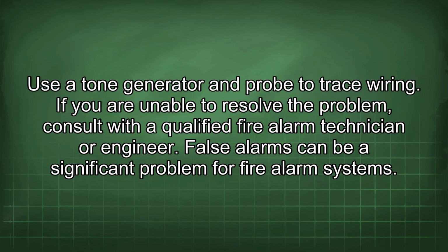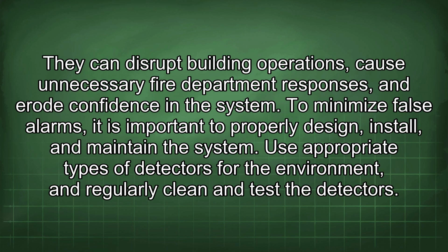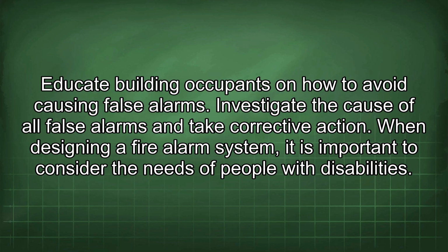False alarms can be a significant problem for fire alarm systems. They can disrupt building operations, cause unnecessary fire department responses, and erode confidence in the system. To minimize false alarms, it is important to properly design, install, and maintain the system. Use appropriate types of detectors for the environment, and regularly clean and test the detectors. Educate building occupants on how to avoid causing false alarms. Investigate the cause of all false alarms and take corrective action.